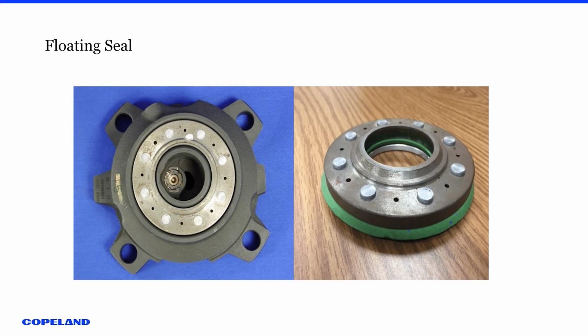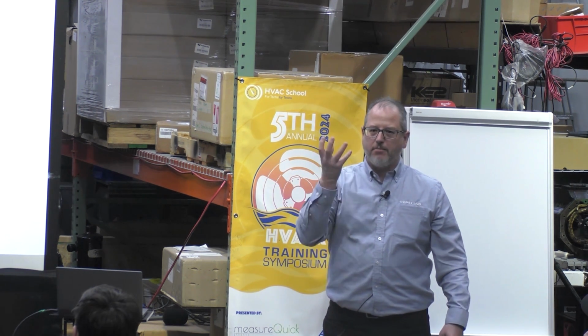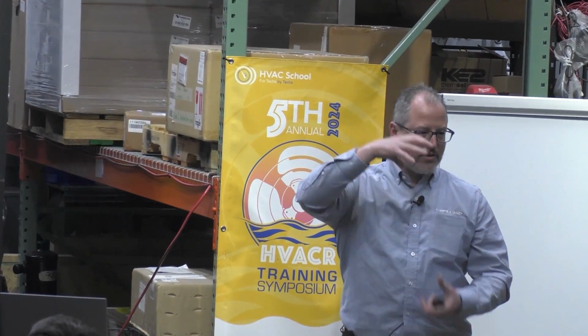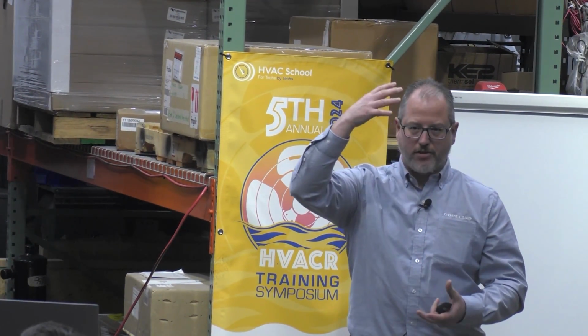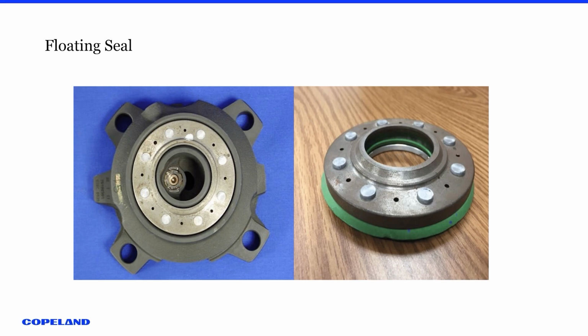Our floating seal, and I'll show you where this goes in a second here, is kind of like a donut, a flat donut. It's aluminum on one side, cast iron on the other. But you can see the little ridge right here. That ridge goes up against that muffler plate, and when it's pushed up, it separates the 2 pressures. So we have high pressure on top and the low pressure on the bottom. When our compressor shuts off, that goes down, and now the pressures equalize inside of our compressor.